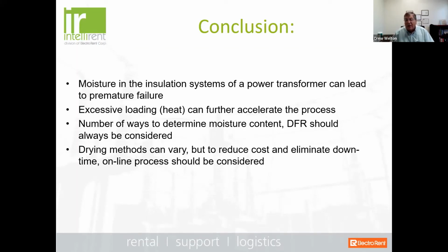And this is one of the problems that we're facing right now, because regular maintenance in substations is being put off, because the loads are so high based on the extremely high temperatures across the country. But basically, your operating temperature has to do with the loading capacity of the transformer itself. So this is important to know, because if you're overloading a transformer, loading it beyond its rating, that's going to cause the excessive heating.